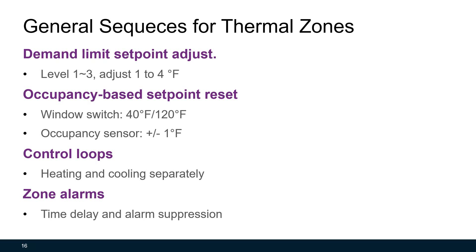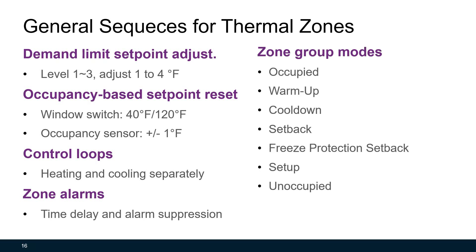Time delay for alarms reduces false alarms that can easily be generated during control mode changes. For zone control, the guideline defines these zone group control modes: occupied and unoccupied modes are straightforward. Setup and setback modes, as well as warm-up and cool-down modes, are also covered. Freeze protection setback mode is a special situation to prevent AHU coils from freezing during cold winters. Warm-up and cool-down modes are related to the optimal start algorithm.